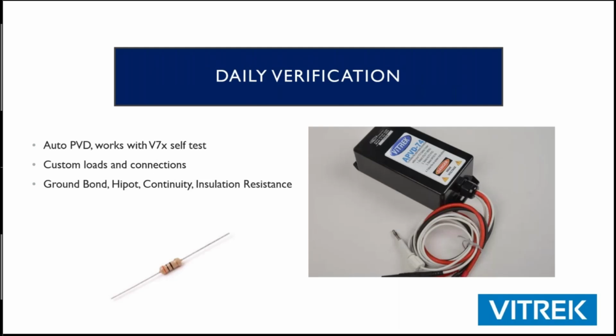So that daily verification, in a lot of the UL standards, they will call out for using a 120k ohm resistor, and it should fail if you connect a 120k ohm resistor, which works. It's fine. What we like to do is take it one step further. So the APVD, which is an extension of the self-test for the V7X, basically you would disconnect your test leads, plug this in, and run the APVD test. It's a known resistance value for both HIPOT insulation resistance and ground bond. We're going to check that at a variety of voltages, verifying the current, from as low as a few hundred volts up to, I believe, 3,500 in that product. And what it does is it makes sure that we can distinguish a good product from a bad product, that we can fail a bad DUT and pass a good DUT. And at the end of the day, that's what the auditors want to see.